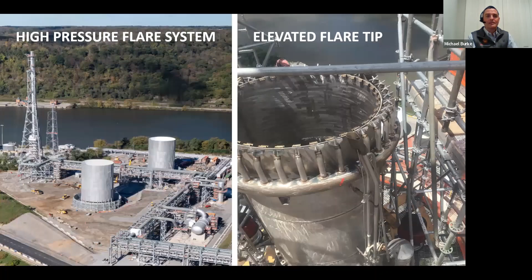Let's maybe take a peek at the high pressure flare system. So there are two major components in this system, one being the ground flares and one being the elevated flare. The ground flares, those are the two metallic cylinders you see in the picture on the left. And the way our system is set up, if there's a need to flare, the initial flow will be routed to the ground flares, and that minimizes or even eliminates the usage of going to the elevated flare. And the benefits of those ground flares: they have an increased capacity for smokeless flaring that's based on their engineering design. And due to that shielding that you see around them, there's less light emitted, less sound emitted from these two ground flares. And for the majority of our startup, we expect that any flaring required is contained within these ground flares.